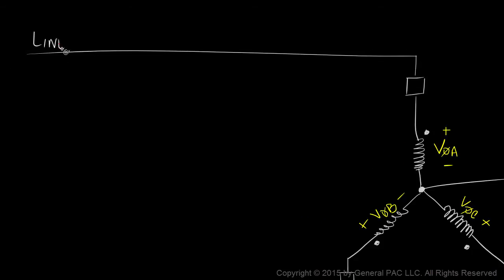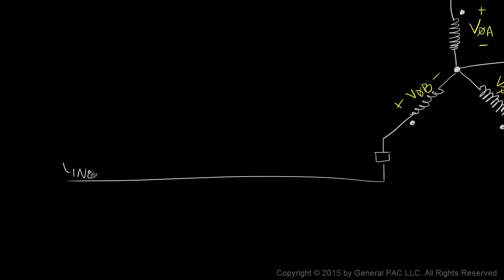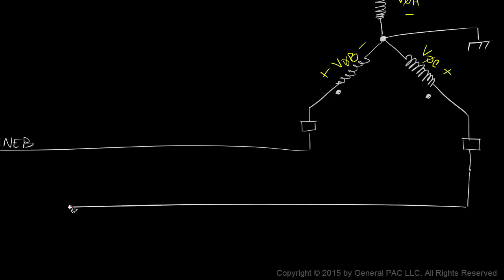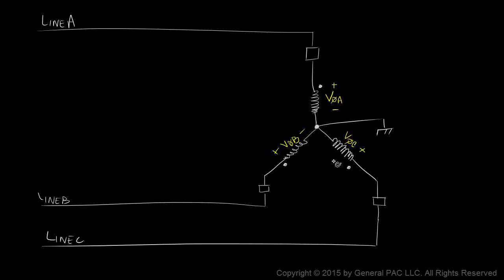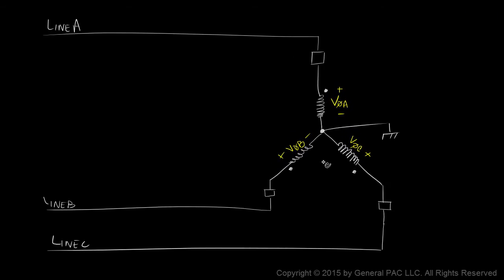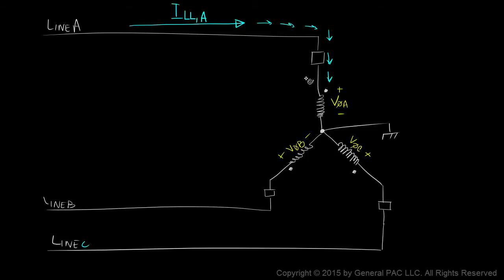Line A, line B, and line C are all connected to their respective bushings. For a Y-connected transformer, we can expect that the line-to-line current and phase current to be equal. This illustration shows very clearly that the line-to-line current for line A flows directly into the polarity side of winding A, so the line-to-line current equals the phase current.